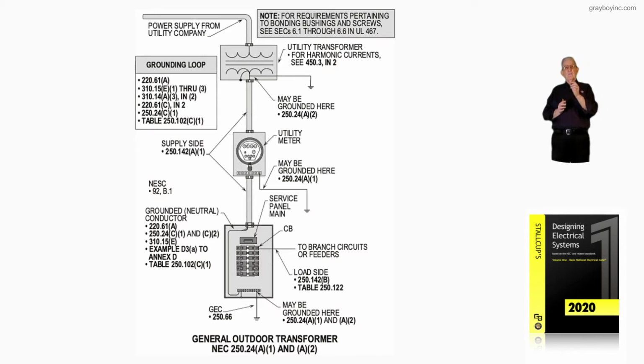220.61(C)(2) and read informational note 2, it again deals with that neutral conductor. And the golden rule for sizing and determining ampacity of conductors is 310.14(A)(3), and that would be Items 1 through 4. Very important that we know that. Now in the illustration, we're just using Item 2 there. You'll have Item 1, Item 2, Item 3, Item 4 that deals with correction factors, adjustment factors, sizing the load, termination values, and all that. So engineers have always said that's the golden rule. It used to be in the ASHRAE Fundamentals Handbook only, but now it's in the NEC, 310.14(A)(3), Items 1 through 4.